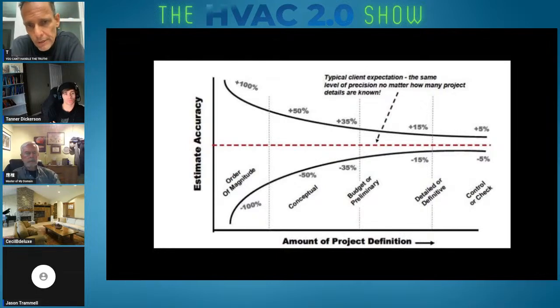Somebody that has experience running manual J's, running blower doors, and doing home performance is bringing a perspective to this that's kind of black belt-ish. You may do this, but your perspective comes from a level of experience most people don't have. If we're going to solve for the broader marketplace, we need to take them from a place of not having a whole lot of knowledge and be able to have the conversation with the homeowner at each step. You can do a load calc, then bring the blower door to get it more accurate, then true it to energy use to get it even more accurate. So at the end of the day, what size equipment are you putting on that 2,100 square foot house?